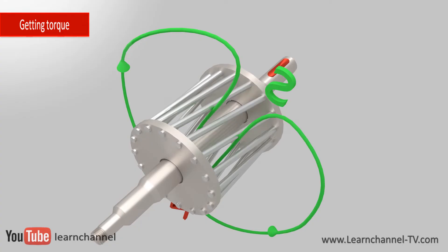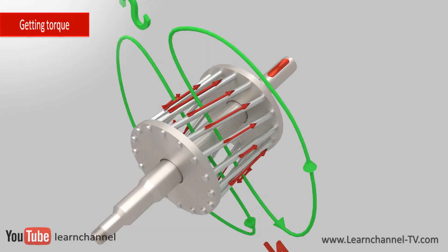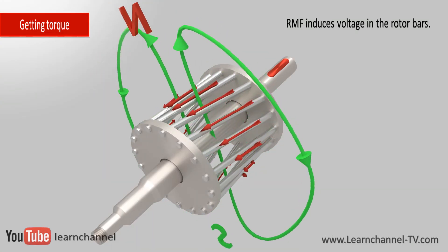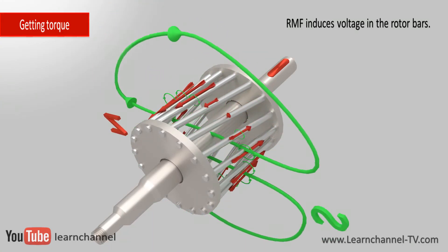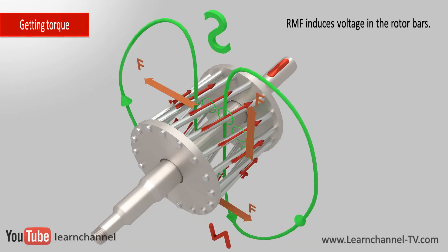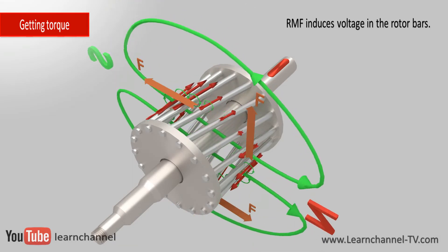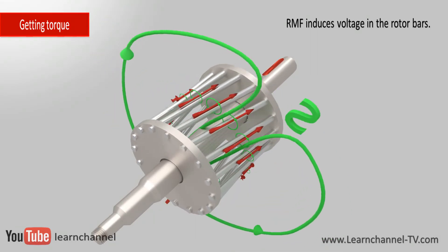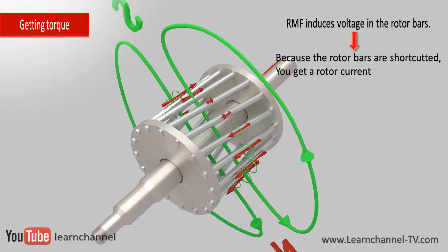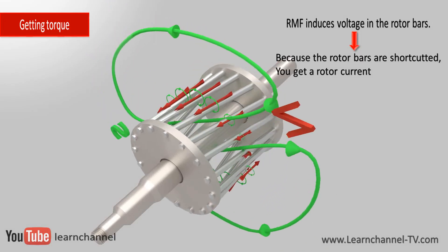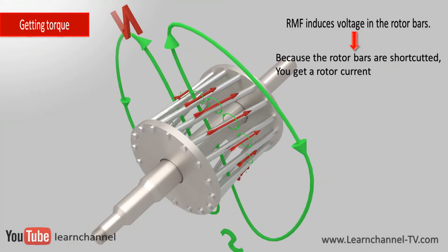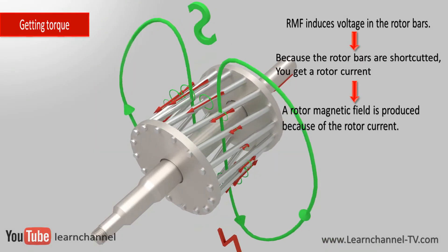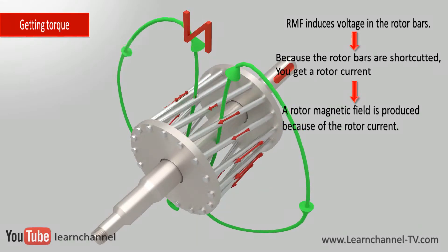As the stator magnetic field rotates, voltage is induced within the bars of the rotor. As the rotor bars are short-circuited at both ends, there is a closed path for the flow of current. This, in turn, produces its own magnetic field in the rotor bars, which opposes the magnetic field of the stator.